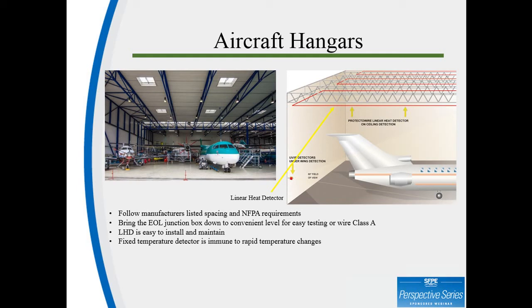If you design or install a Class B configuration, we recommend locating your end-of-the-line box approximately 8 to 10 feet off the floor height. This will enable whomever is servicing or testing the system to do all the necessary testing with only a small step ladder, rather than requiring a scissor lift to open up a junction box 30, 50, maybe 80 feet in the air.